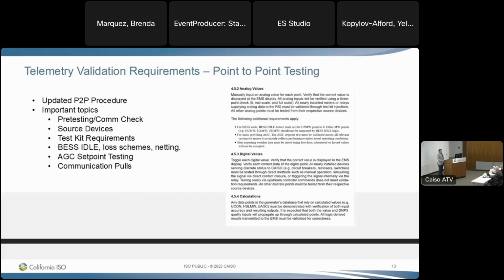So some important topics for pre-testing, ComCheck. We really want to encourage and require that pre-testing. We want to encourage a DNP3 master emulator so that you can really simulate the CAISO rig communication so that there's very little ambiguity and less surprises during the actual point-to-point test. For the ComCheck, we just request that you give us 5 days in advance of your point-to-point appointment, and that would be 5 business days, right? So that we have time to review the telemetry and meters, activate the certificates on the rig, and then have time to plan for that actual point-to-point test date.